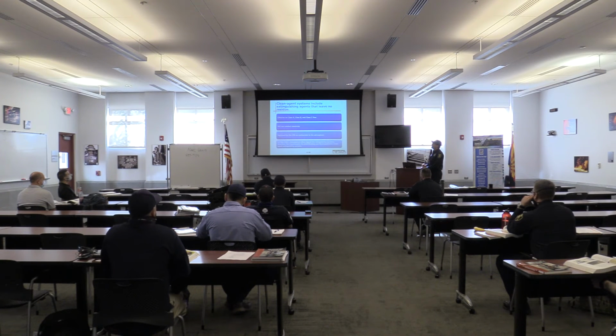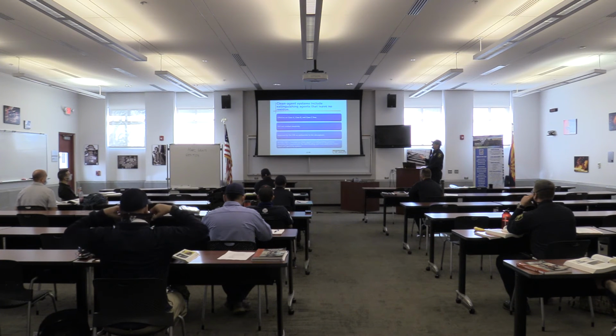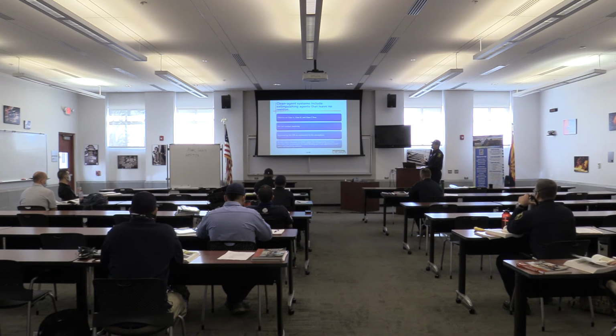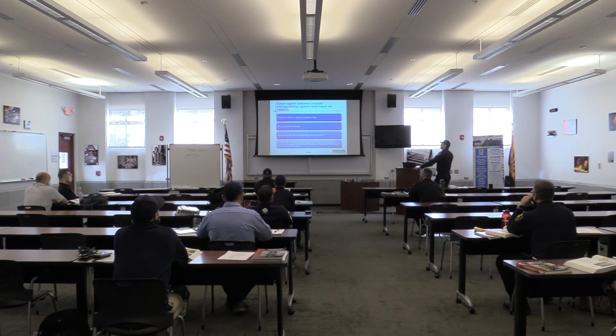All right. So clean agents are effective on Class A, B, and C fires. They don't conduct electricity, and the biggest part is they don't have a hazardous health component to them. And they're approved by the EPA. They don't destroy the ozone layer. So that's a big plus for these systems. And as we'll talk briefly about, a lot of these are replacing halon systems.